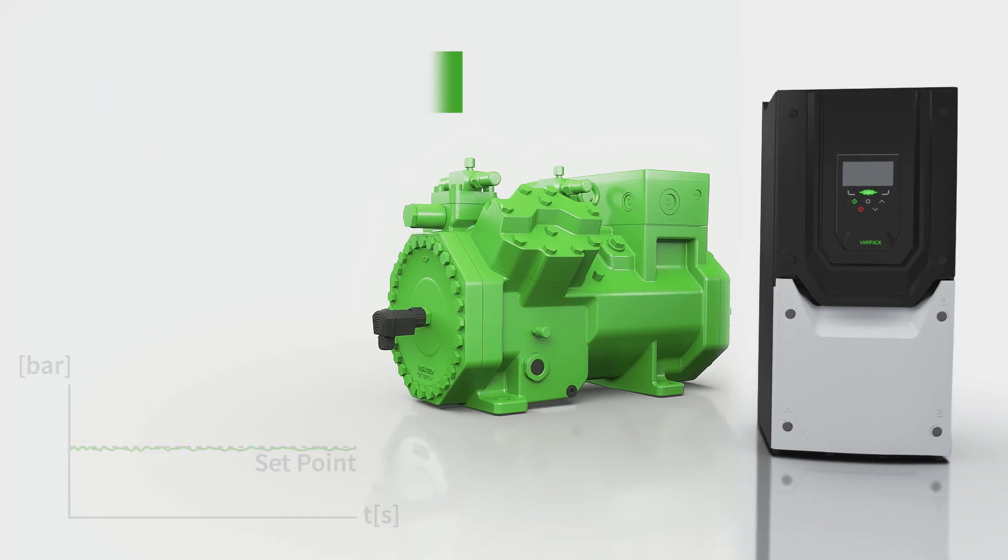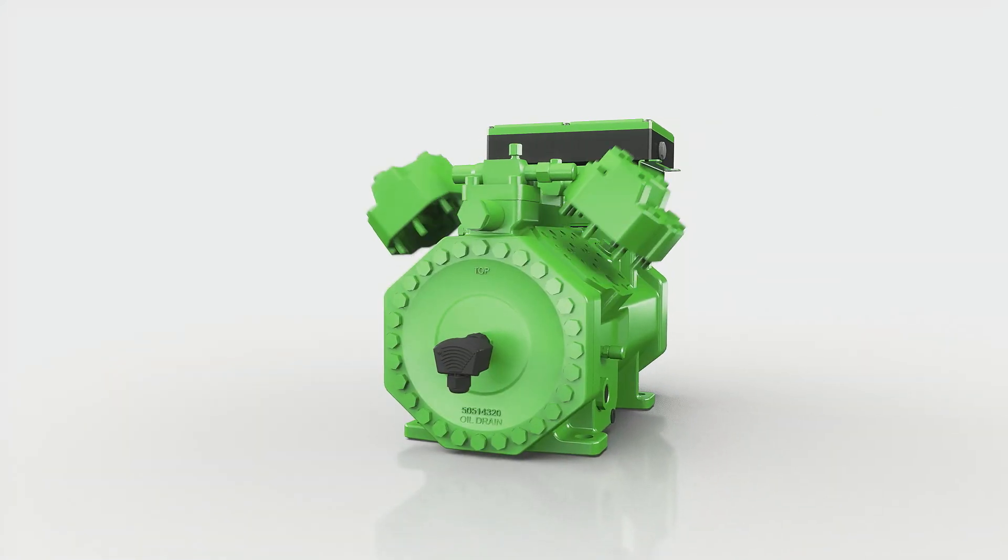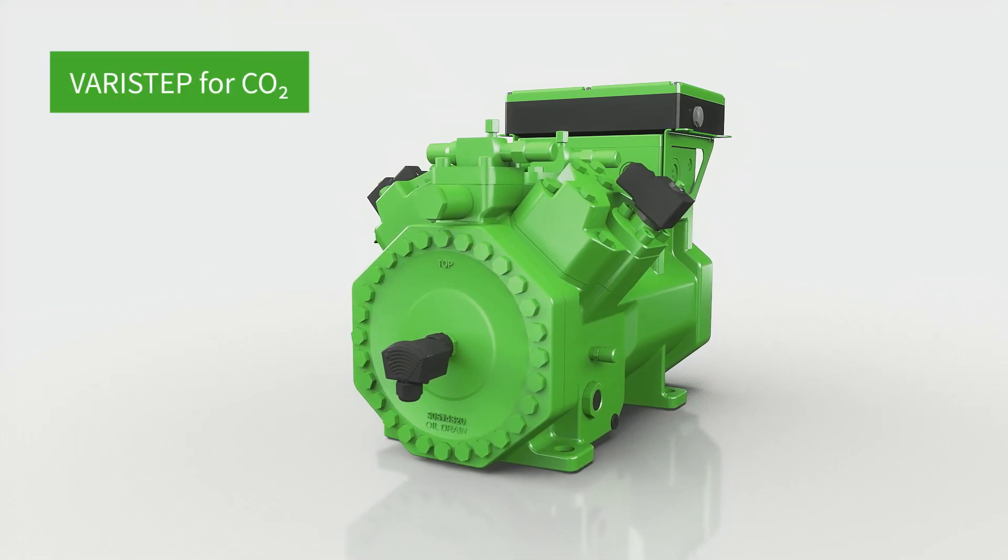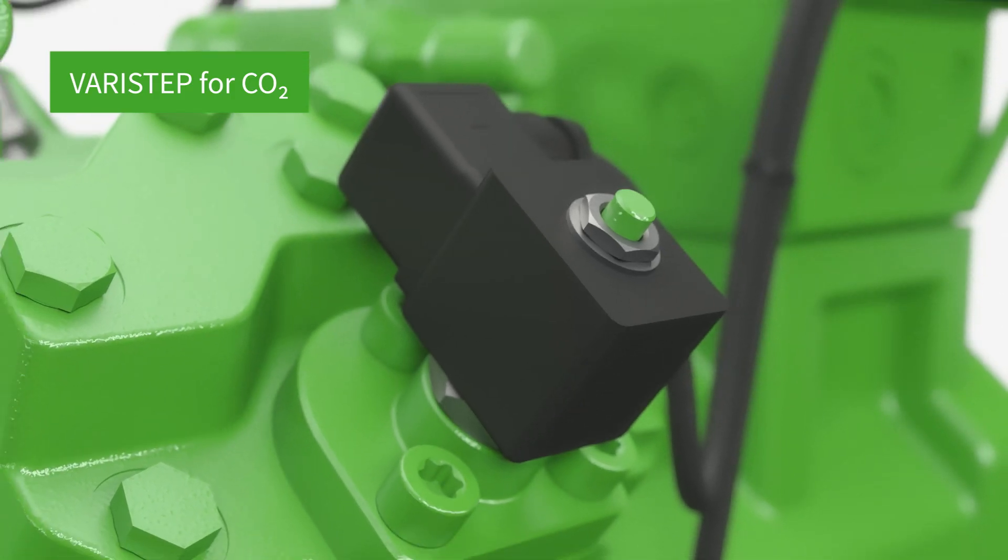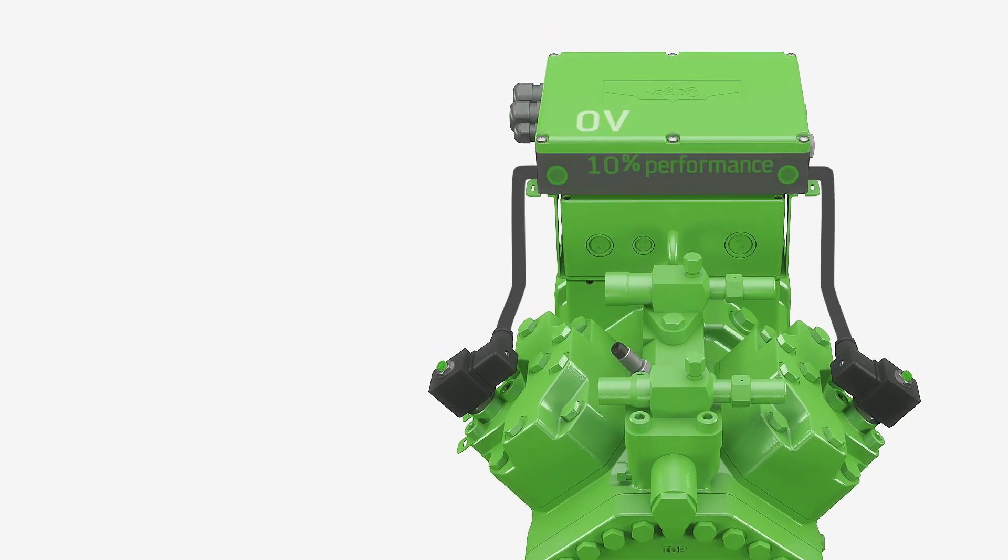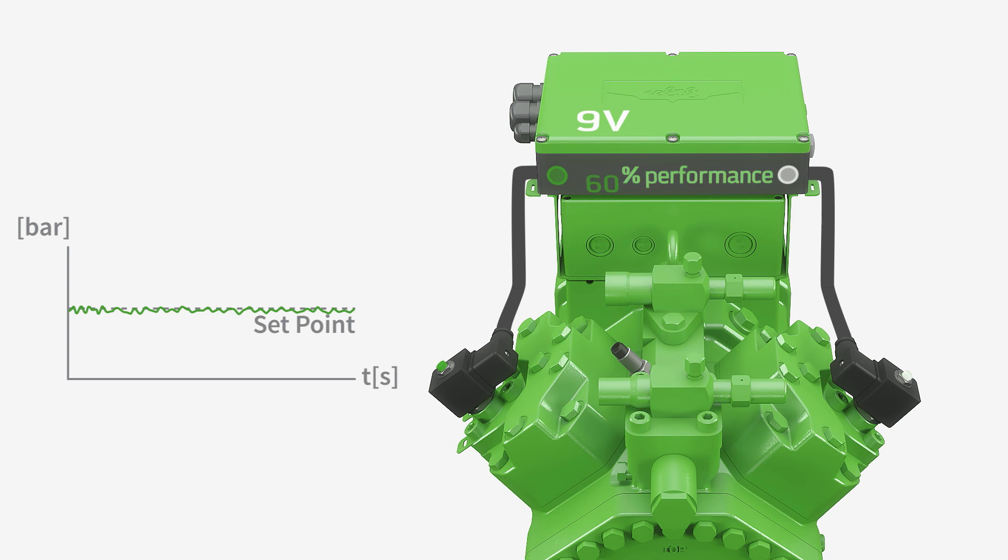As another option, Bitzer offers a new form of mechanical capacity control: VariStep for CO2. The intelligent VariStep mechanical capacity control enables virtually stepless operation between 10 and 100%, is designed for high pressure in trans-critical CO2 applications, and allows for a compact design.